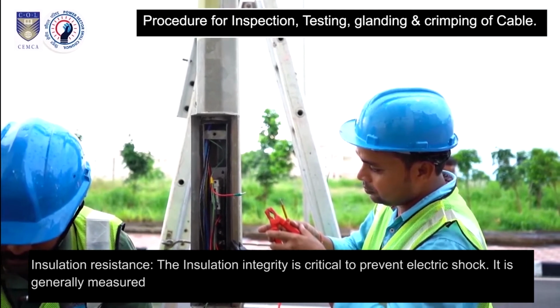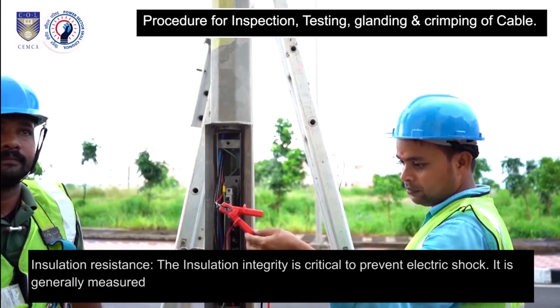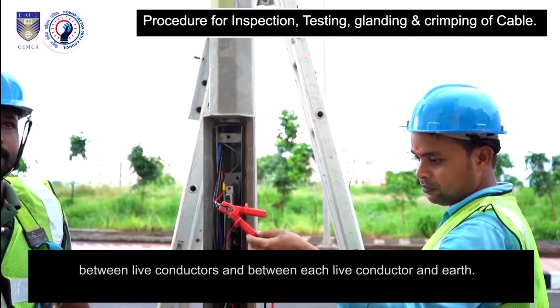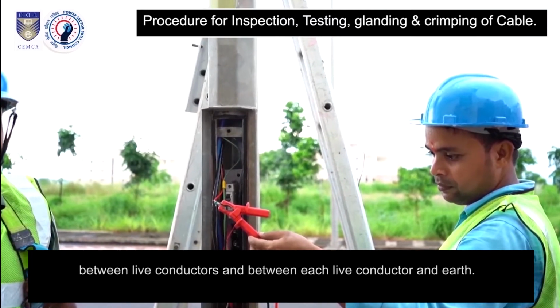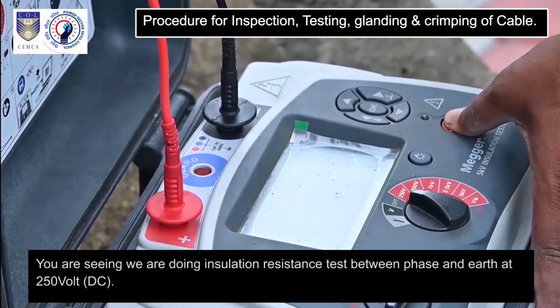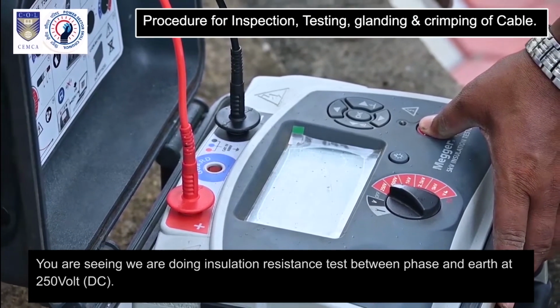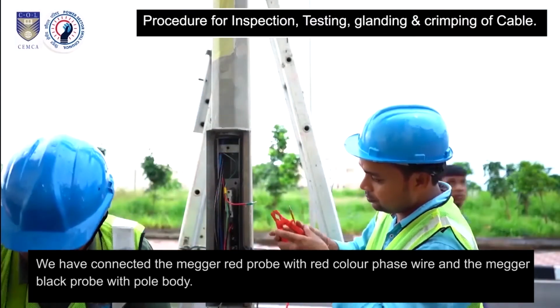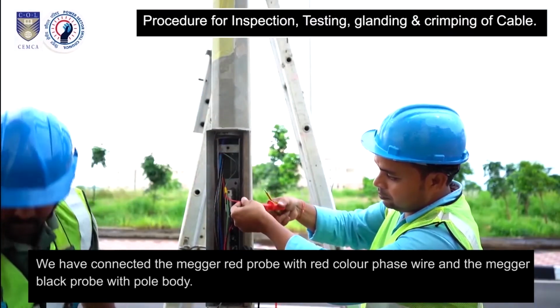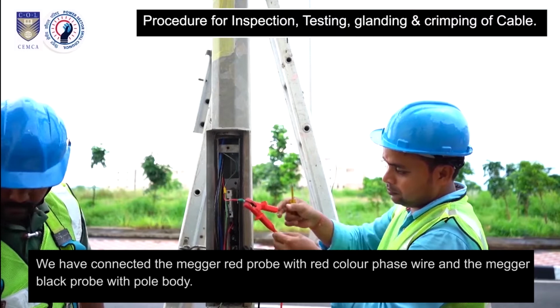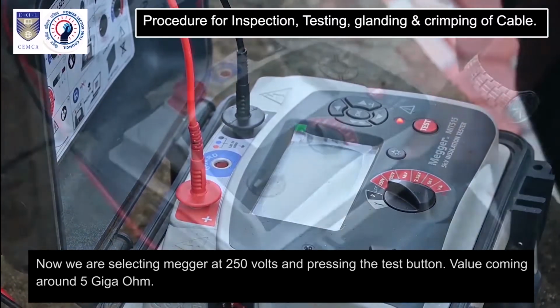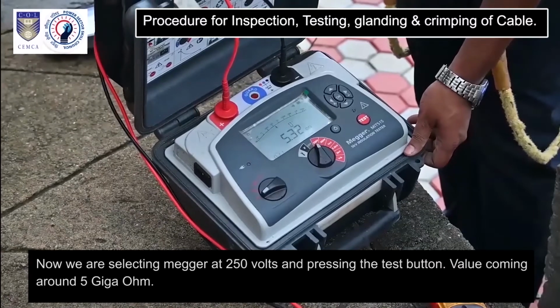Insulation resistance. The insulation integrity is critical to prevent electric shock. It is generally measured between live conductors and between each live conductor and earth. You are seeing we are doing insulation resistance test between phase and earth at 250 volt DC. We have connected the Megger red probe with red color phase wire and the Megger black probe with pole body. Now we are selecting Megger at 250 volts and pressing the test button. Value coming around 5 gigaohm.